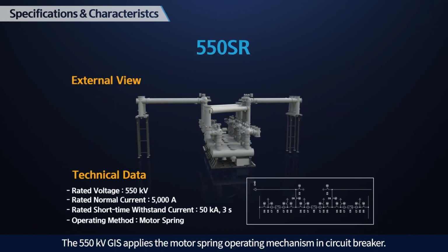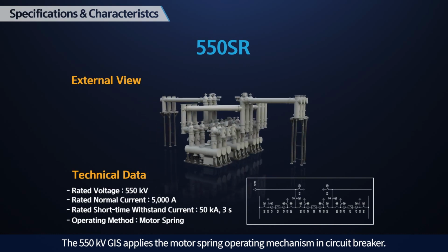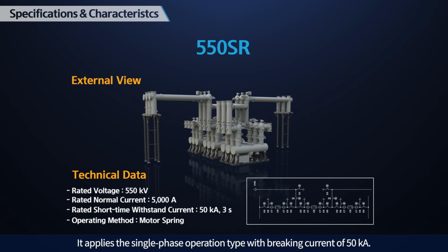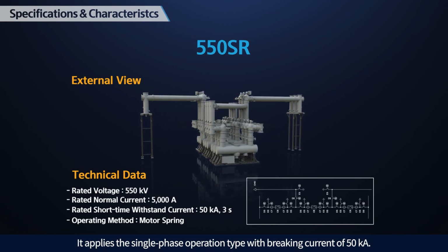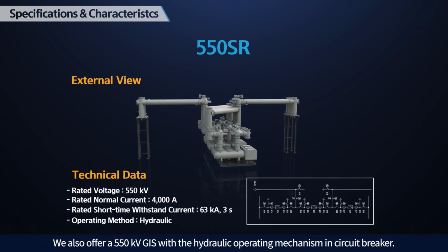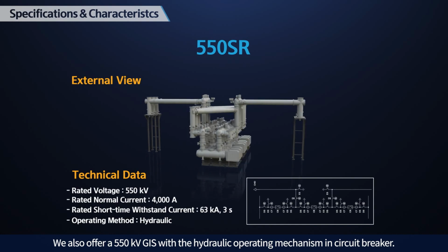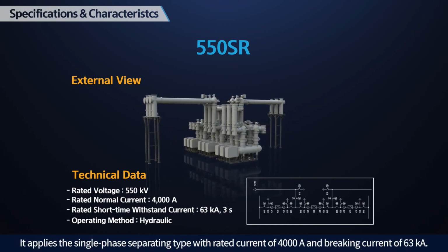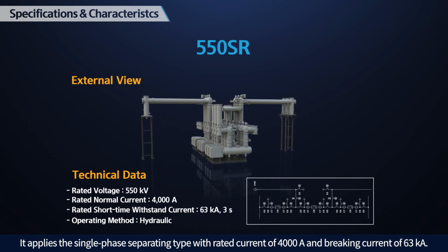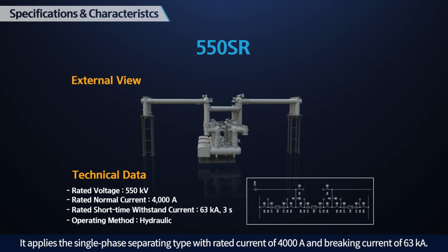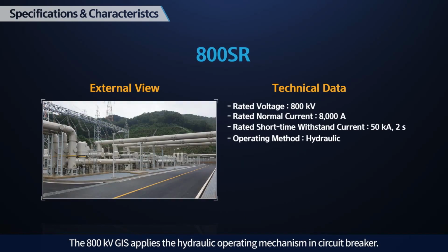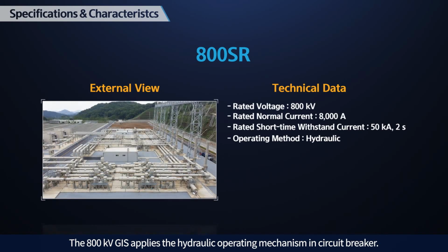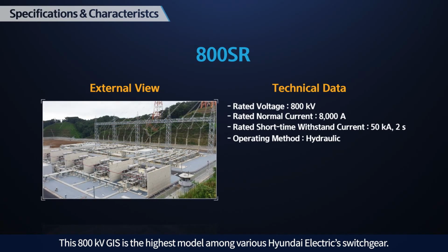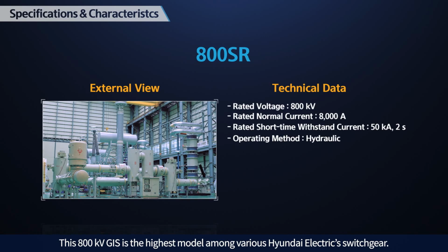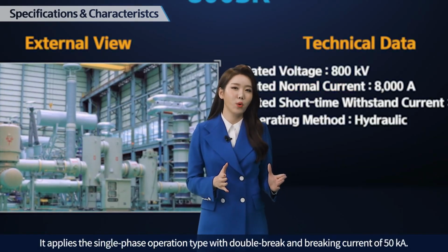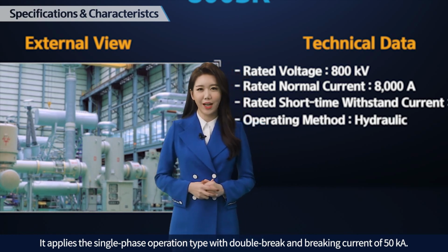The 550 kV GIS applies the motor spring operating mechanism in circuit breaker. It applies the single-phase operation type with breaking current of 50 kA. We also offer a 550 kV GIS with a hydraulic operating mechanism in circuit breaker. It applies the single-phase separating type with rated current of 4,000 ampere and breaking current of 63 kA. The 800 kV GIS applies the hydraulic operating mechanism in circuit breaker. This 800 kV GIS is the highest model among various Hyundai Electric's switchgear. It applies the single-phase operation type with double-break and breaking current of 50 kA.